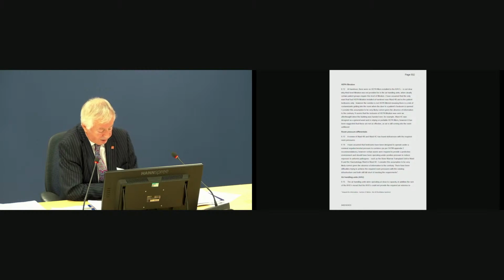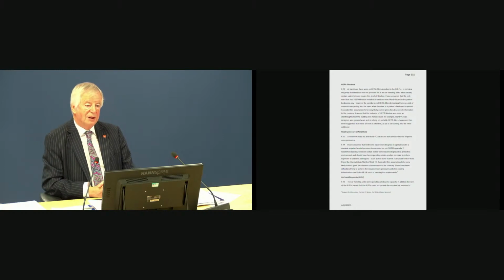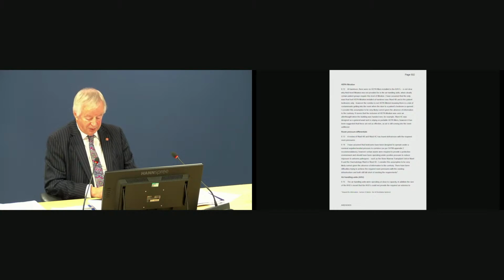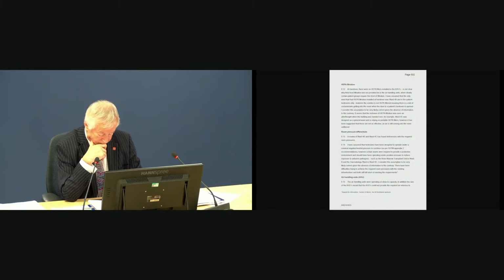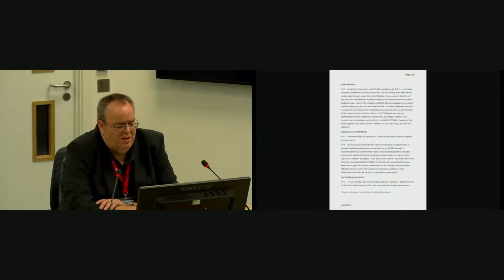the air handling units, that from an engineering perspective must be one of the significant issues. Can the air handling unit do what you want it to do? And the point you're identifying here is, well, what happens if they're already close to capacity? Is that right? Yes, and it is fair to say that a brand new unit working at 100% capacity will lose some degree of performance over time due to wear and tear.